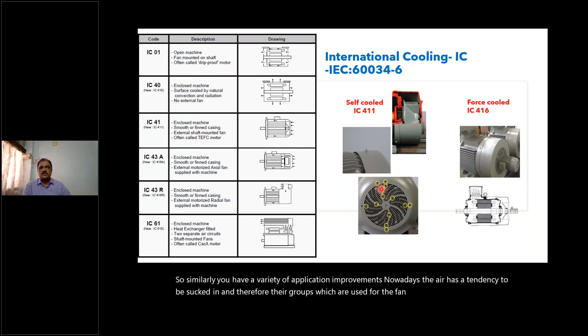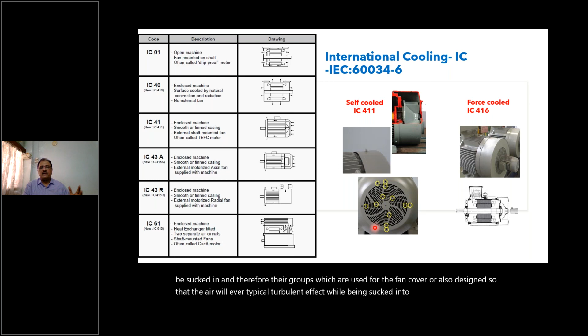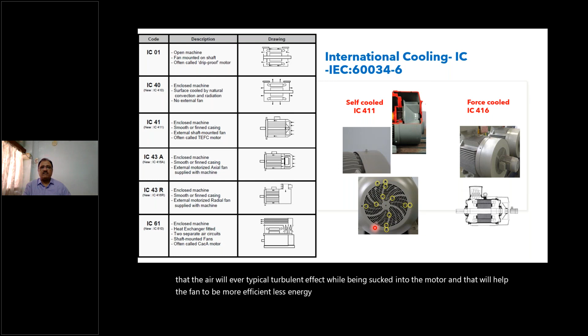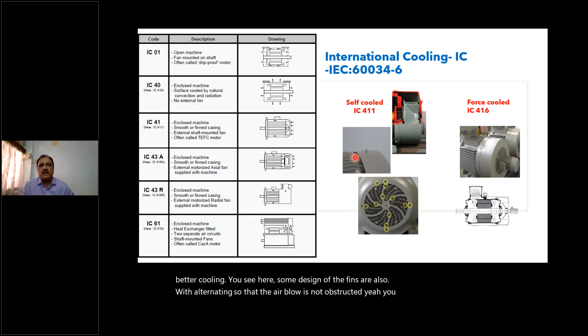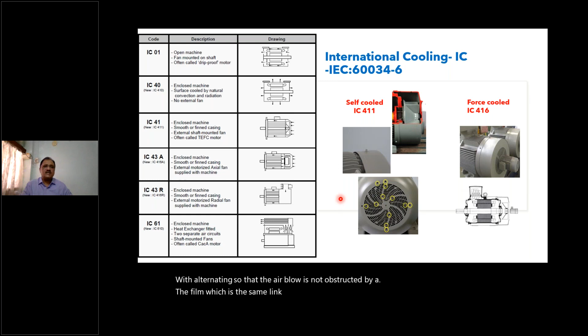So similarly, you have a variety of application improvements nowadays. The air has a tendency to be sucked in, and therefore the grooves which are used for the fan cover are also designed so that the air will have a typical turbulent effect while being sucked into the motor, and that will help the fan to be more efficient, less energy consuming, and at the same time the motor will have a better cooling. You see here some design of the fins are also alternate so that the air blow is not obstructed by a fin which is of the same length or the same dimension. So these are some technologies which have come for improving the performance of the motors.